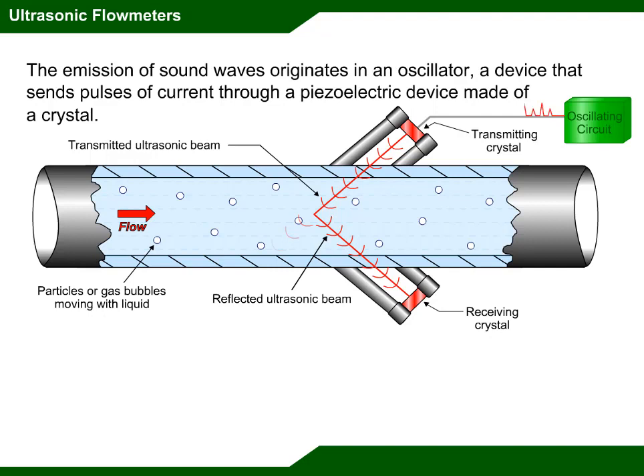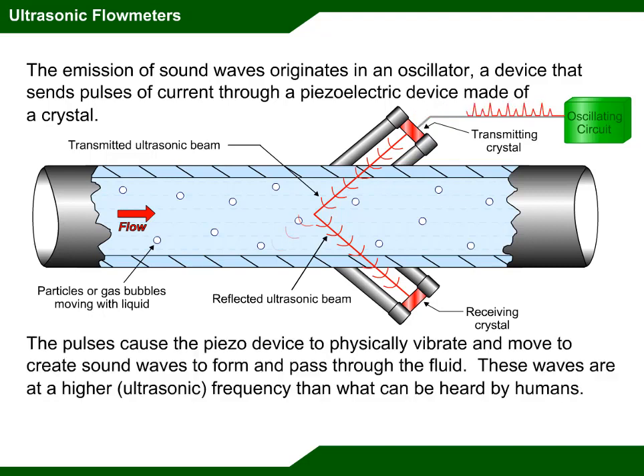The emission of sound waves originates in an oscillator, a device that sends pulses of current through a piezoelectric device made of a crystal. The pulse causes the piezo device to physically vibrate and move, creating sound waves that form and pass through the fluid. These waves are at a higher ultrasonic frequency than what can be heard by humans.